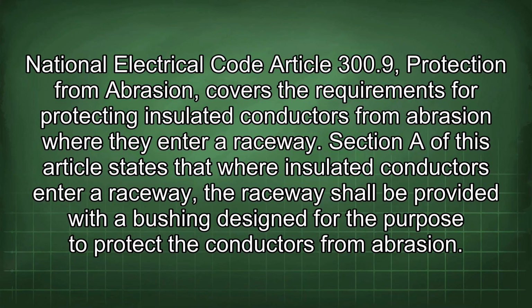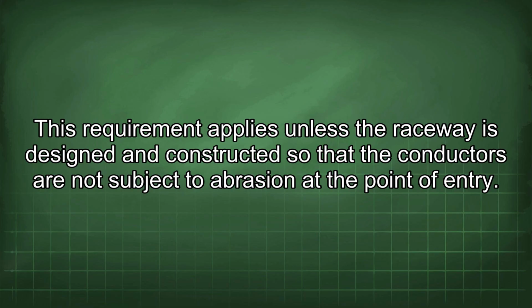National Electrical Code Article 300.9, Protection from Abrasion, covers the requirements for protecting insulated conductors from abrasion where they enter a raceway. Section A of this article states that where insulated conductors enter a raceway, the raceway shall be provided with a bushing designed for the purpose to protect the conductors from abrasion.